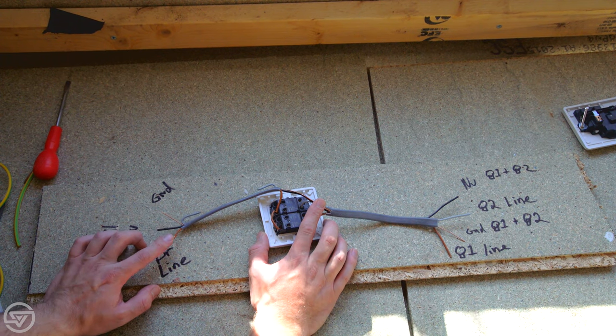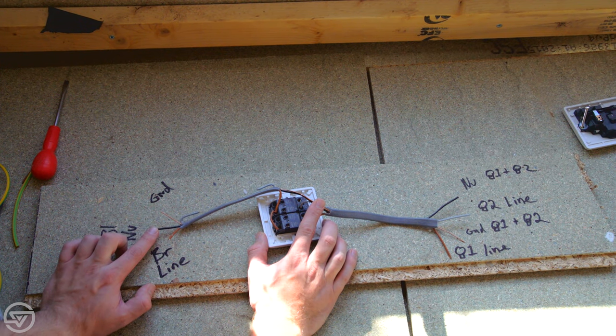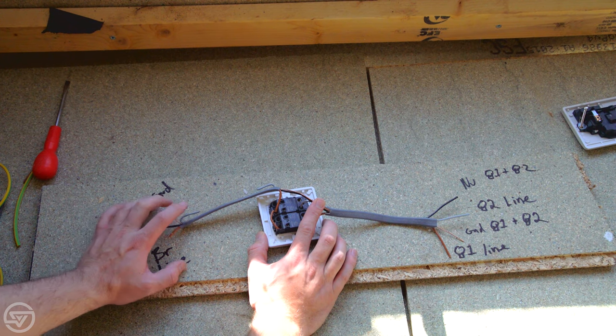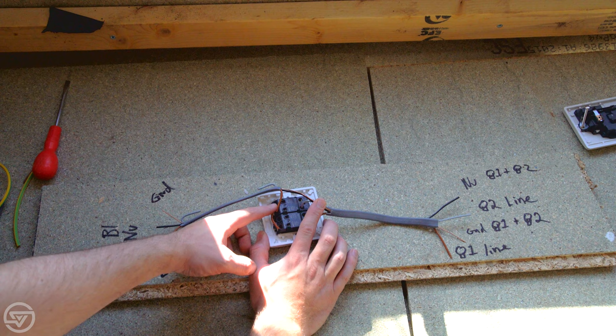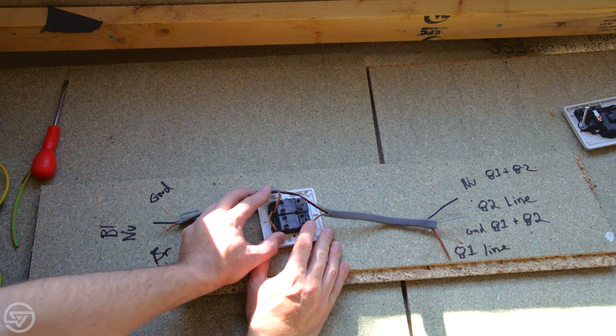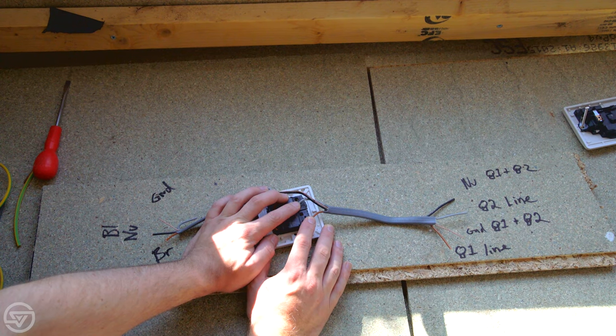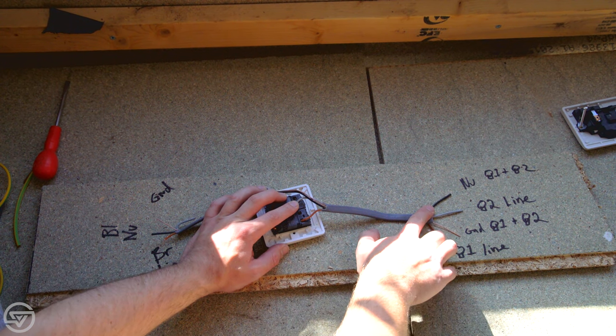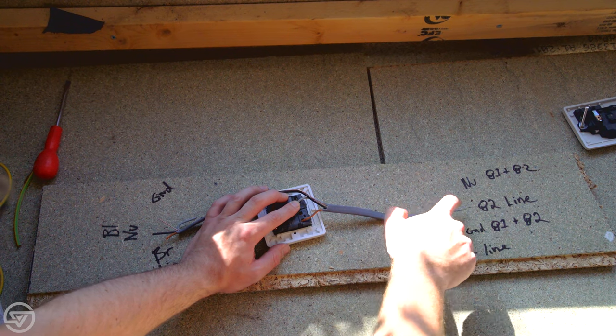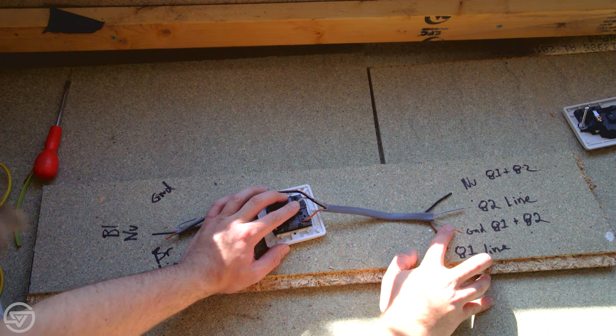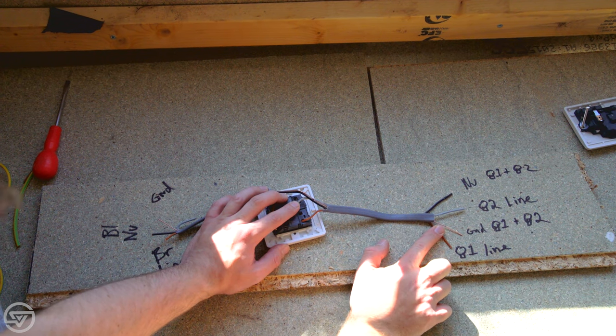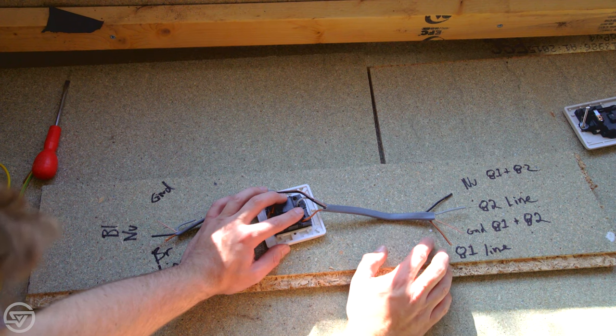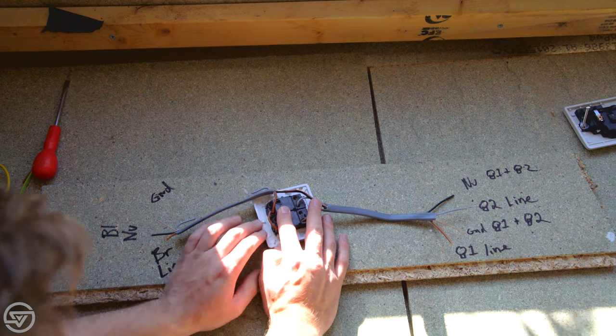I'm using the brown on the supply side for the line, black for the neutral, and of course ground is ground. I'm not using the gray line on the supply side. When I get to the switch, I'm jumping the supply over to both switches, then using the brown and gray wires to supply each of the lighting circuits. The neutral is common for both lights, brown is for light two, and gray is for light one.